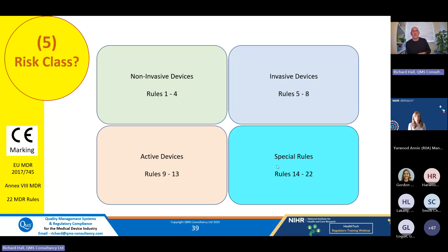Rule 1 says all non-invasive devices are classified as Class 1 unless one of the other rules set out hereinafter applies. Rule 2 talks about non-invasive devices intended for channeling or storing of blood for the purpose of infusion. Rule 3 talks about all non-invasive devices intended for modification of biological or chemical compositions of human tissues. Rule 4 talks about non-invasive devices that come into contact with injured skin. A plaster or a bandage might fall into Rule 4 because they're all non-invasive.